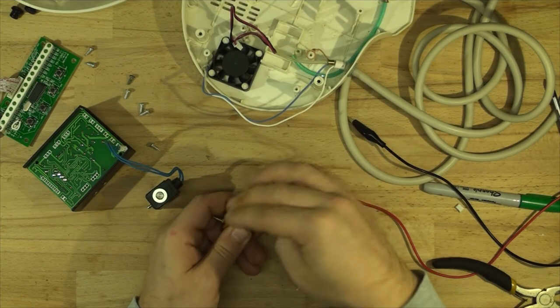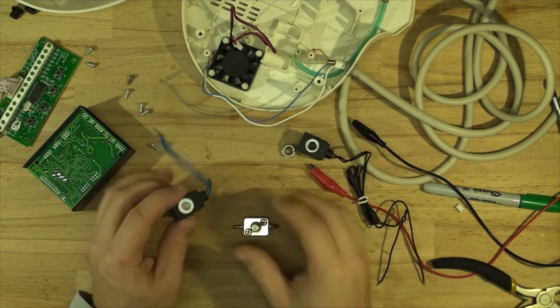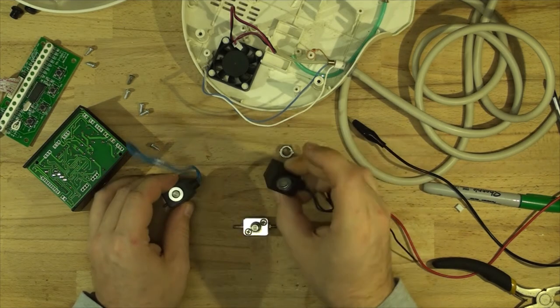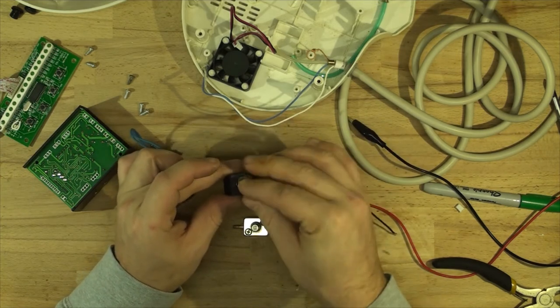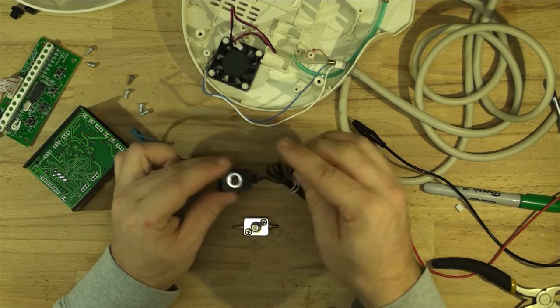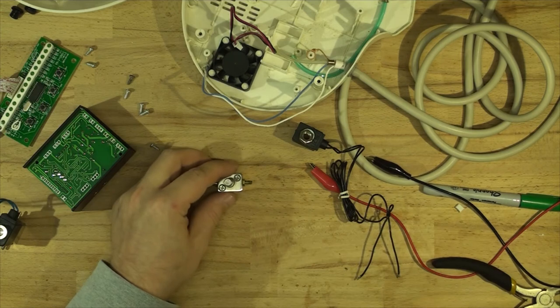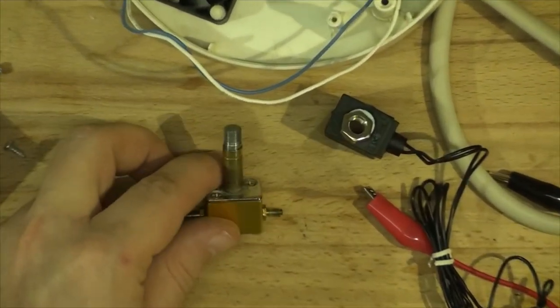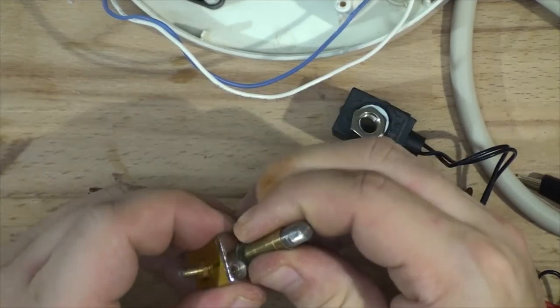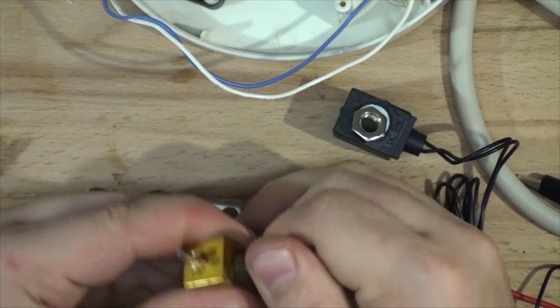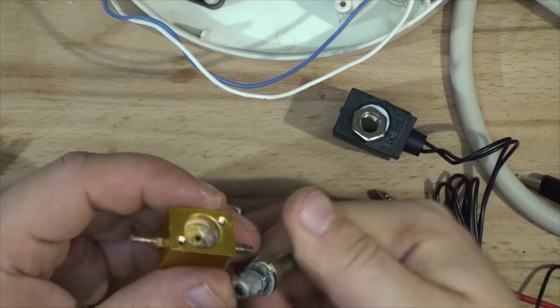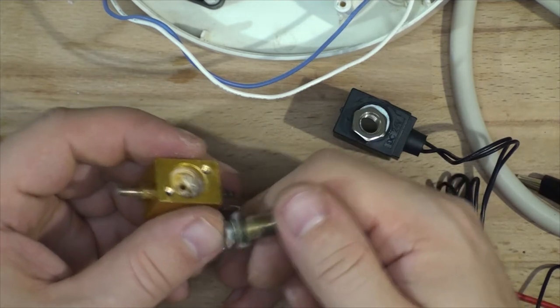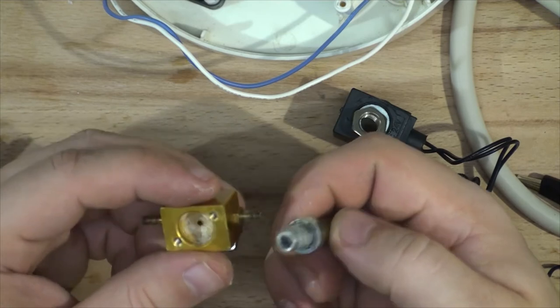Let's take that electromagnet off. It looks like someone's already been inside the solenoid because the nut was wrong way around. It was threading into the plastic, but it should be this way because you can see it's got that little lip. So we'll pull apart this existing solenoid and have a look. I'll zoom in so you can see better. It probably just needs cleaning. I doubt it's faulty. And it's all gunked up. The solenoid is good, it's just very filthy dirty.